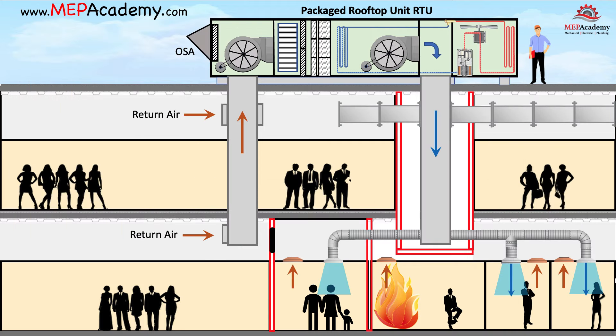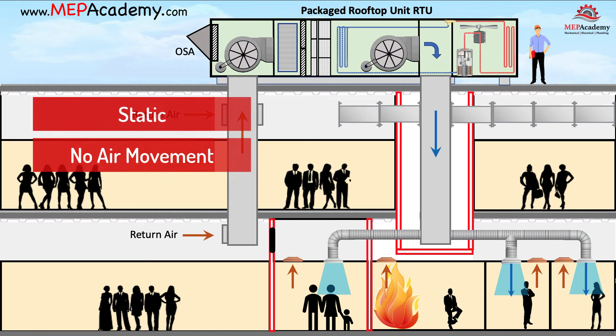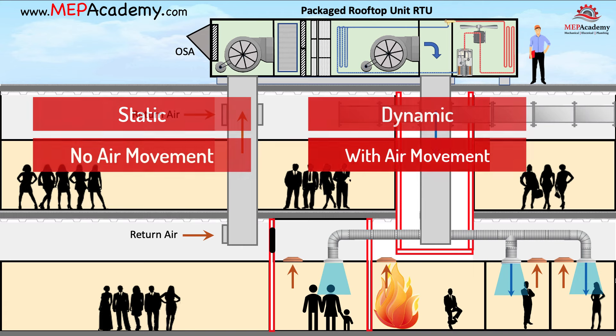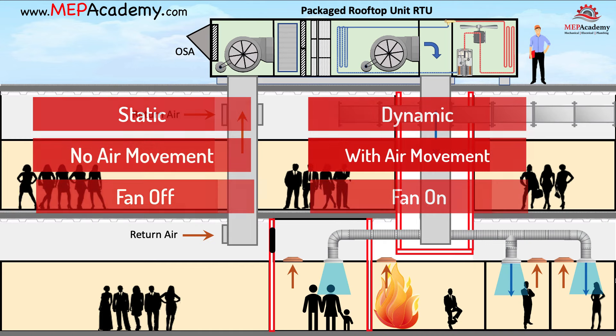Fire dampers are classified for use in a static system. A static system is an HVAC system designed to stop the movement of air within the system at the indication of a fire. A dynamic system is an HVAC system designed to maintain the movement of air within the system at the indication of a fire. In a static system the fan should be off, while in a dynamic system the fan will be running as part of an engineered smoke control system.